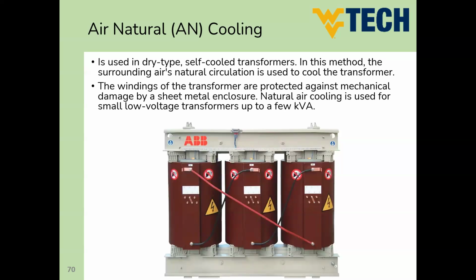Here, for instance, guys, we have an air natural cooling transformer. This is an ABB transformer with a few kVA rating. So this is a dry type self-cool transformer. In this method, the surrounding air's natural circulation is used to cool the transformer. The windings of the transformer are protected against mechanical damage by a sheet metal enclosure. Natural air cooling is used for a small low voltage transformer up to a few kVA. Okay, guys, so small low voltage transformer means it's from medium to low volt, okay? But it's less, or a few kVA, okay? So this is a dry or air natural core.